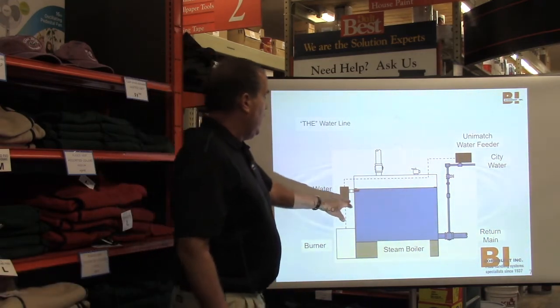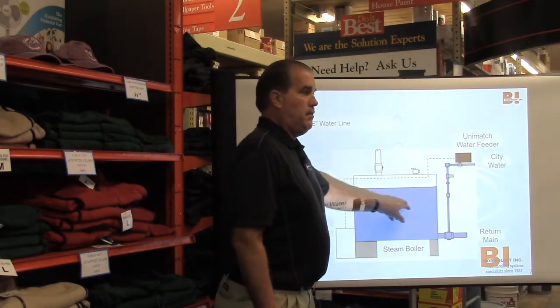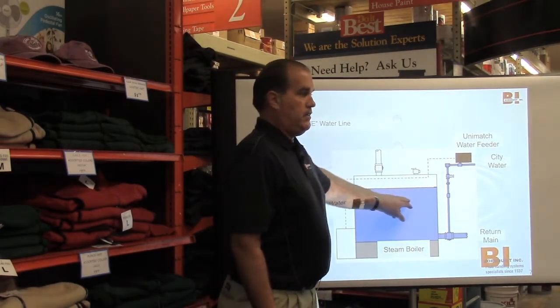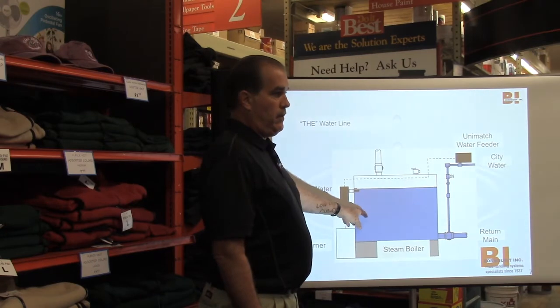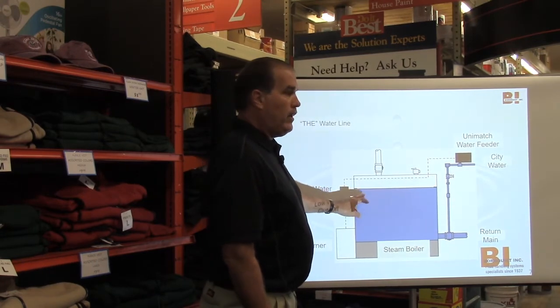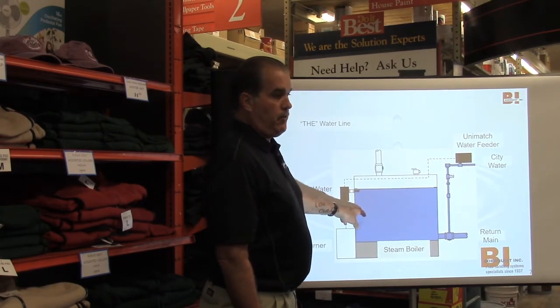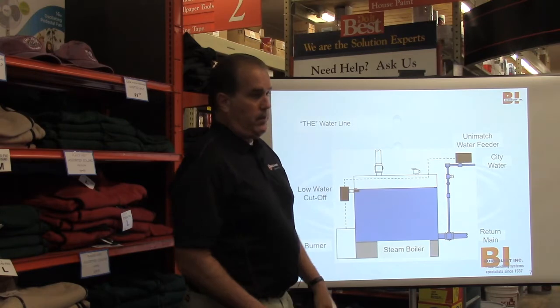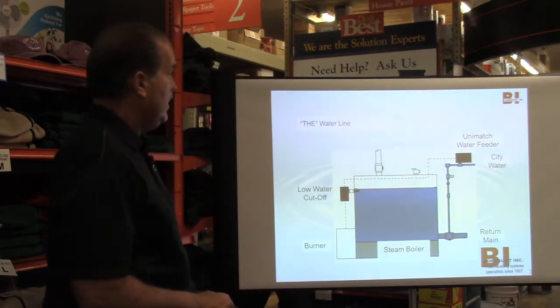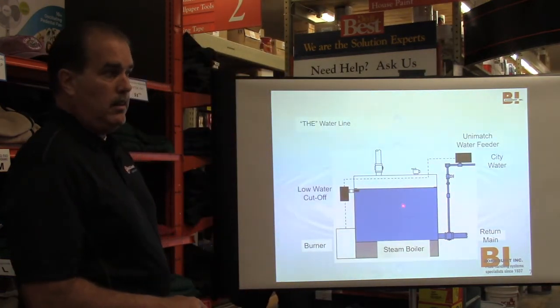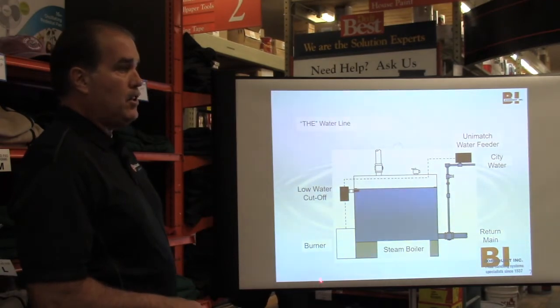Because now your water, the manufacturer has a recommended minimum water line somewhere marked on his boiler. Every boiler maker has it. If that water gets below that, he does not want that burner running. They want you to rectify that and get water back in the boiler, okay? And that's what this probe type low water cutoff is doing: it monitors that water, and once it drops off, it shuts the burner off.